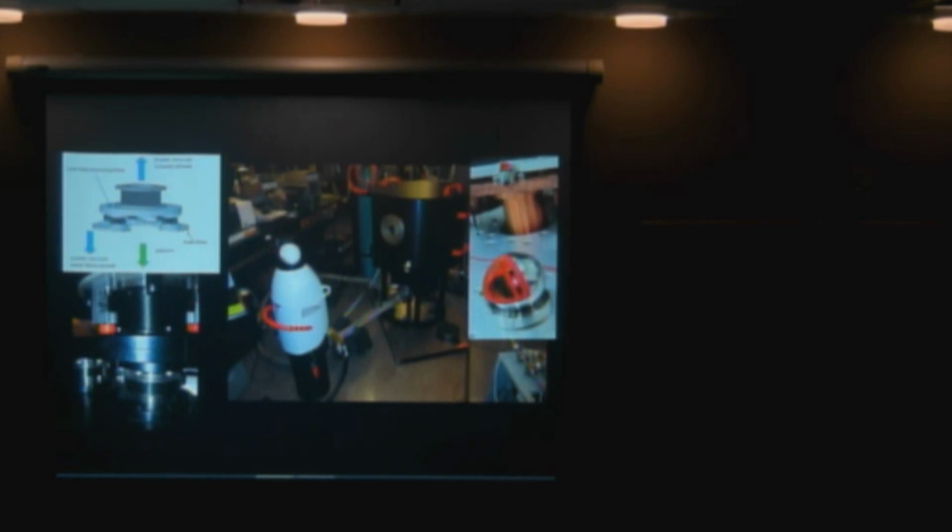And it also can measure how long it takes for the laser beam going from here to the cube and back, so it can calculate the distance very accurately. The accuracy is about 20 microns, which is a fifth of a hair thickness. So it's pretty accurate for absolute measurements, and if you compare two positions to each other, it's even more accurate. One of the interesting tests I could do with this thing was vibration testing.